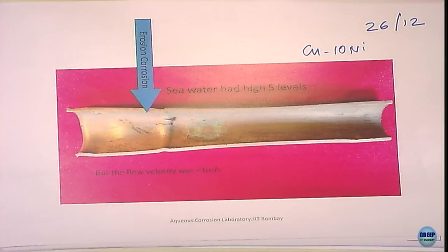When the velocity is less than 1 meter per second and it fails, you do not really look at erosion corrosion as a primary mechanism, right? You can go up to close to about 2 meters flow velocity if it is a copper-nickel alloy.